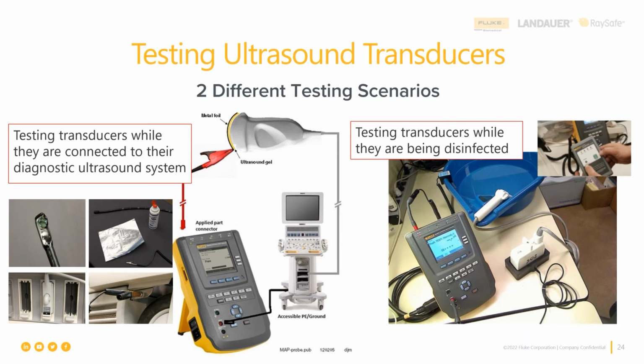If the answer is no, there's a failure on the ULT 800 display, and the central processing technician or the sonographer should call you, the biomed, to come with your safety analyzer and repeat the test by putting your safety analyzer in place of the ULT 800 and making an actual leakage current measurement, which you will send along with that TEE probe, either on exchange for a new one or a repaired one, or send it out for repair and get the same one back.